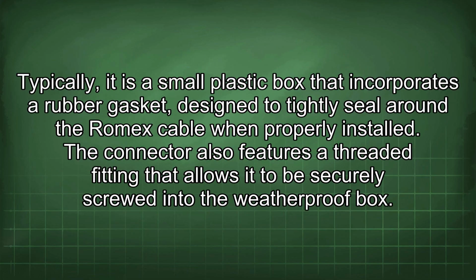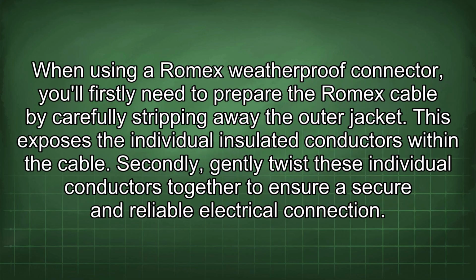Typically, it is a small plastic box that incorporates a rubber gasket designed to tightly seal around the Romex cable when properly installed. The connector also features a threaded fitting that allows it to be securely screwed into the weatherproof box. When using a Romex weatherproof connector, you'll firstly need to prepare the Romex cable by carefully stripping away the outer jacket. This exposes the individual insulated conductors within the cable.